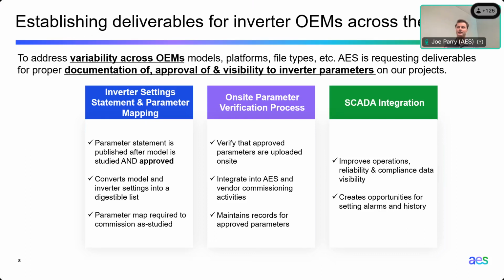What it really does is convert the extensive list of inverter settings that exist in OEM models into a very digestible list of settings that are high impact, such as ride-through settings or droop settings, in that realm of area where we really do care how this inverter is going to operate in relation to our contracts.